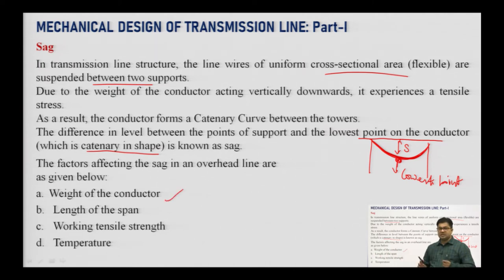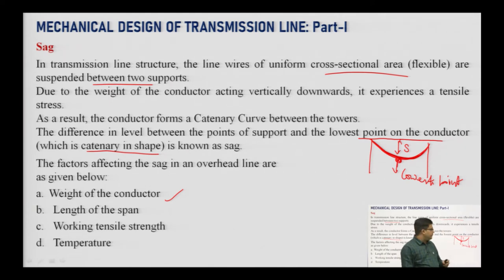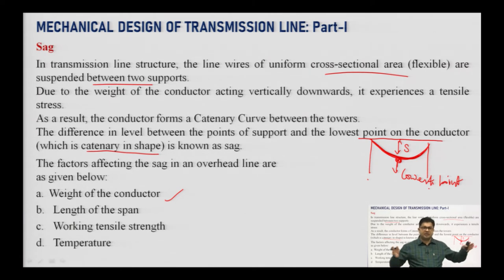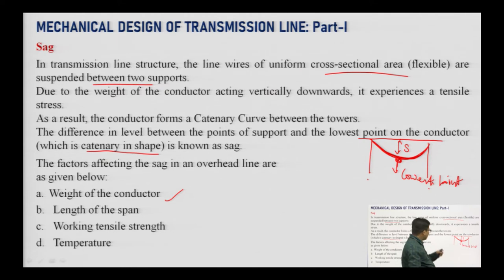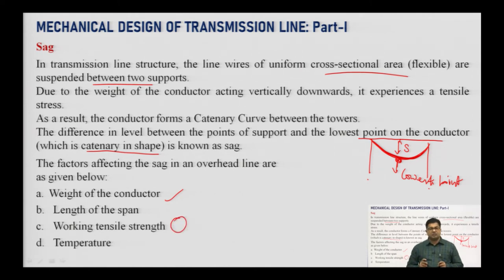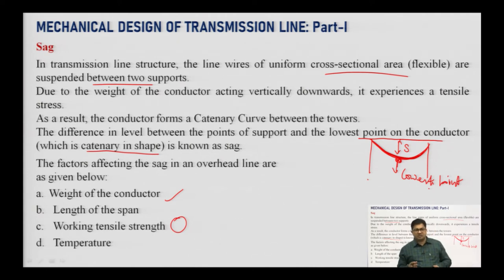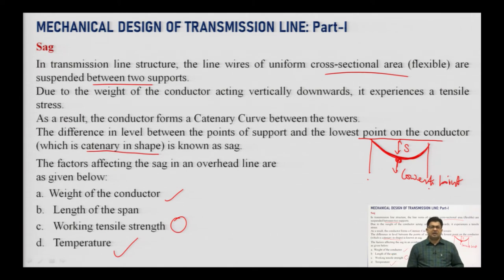The sag depends on several factors. First, the weight of the conductor — if the weight is large, the sag will increase. Second, the length of the span — if the distance between towers is large, the sag will be larger. Third, the working tensile strength — sag is inversely proportional to tensile strength. If tensile strength is high, you can reduce the sag by tightening the wire. Fourth, temperature — as temperature increases, the conductor expands and sag increases.